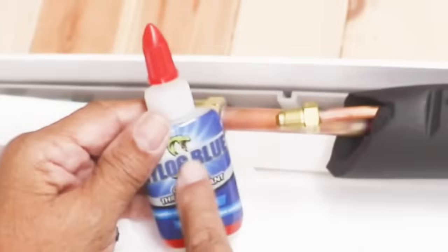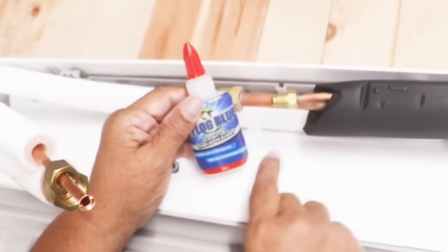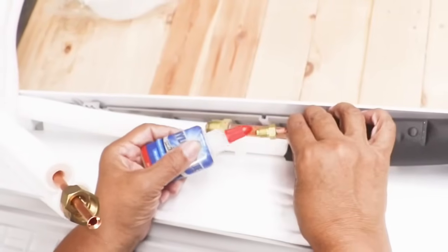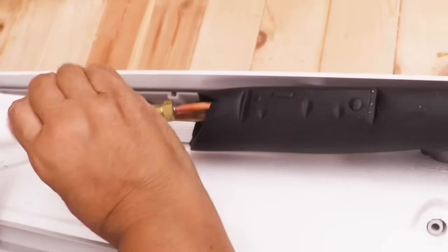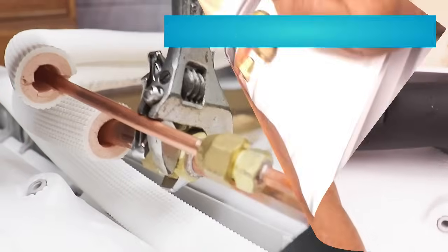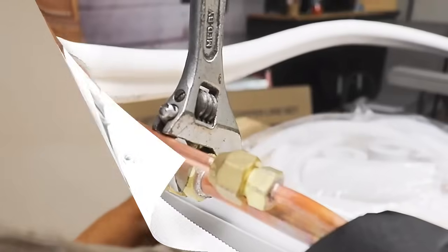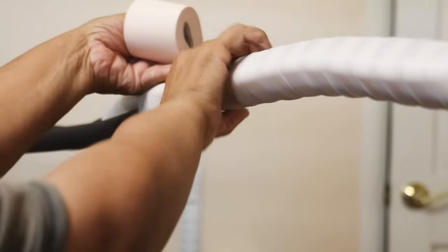We're going to use a little Nylog Blue for our connections — it's compatible with all refrigerants and won't contaminate the system. You don't apply it to the threads, just to the face here. You don't have to use this but it's something I prefer. Then with the tape they provide, wrap the coolant lines and drainage lines. Make it compact enough so that you can fish it through the wall without any resistance.